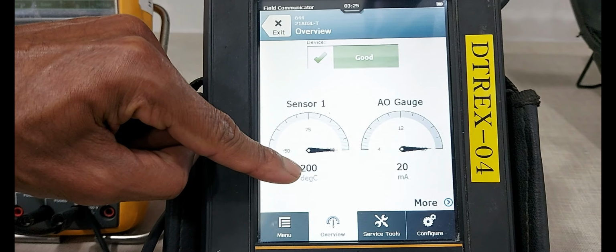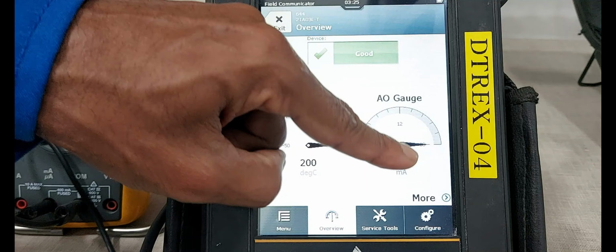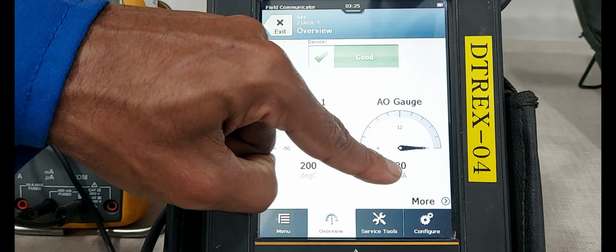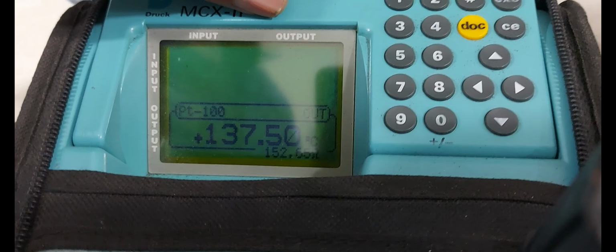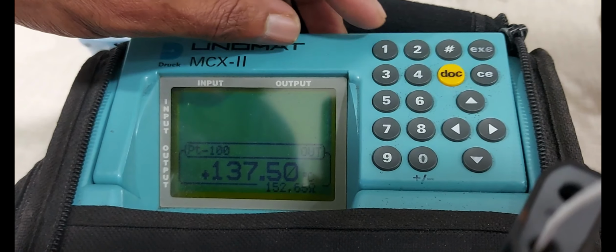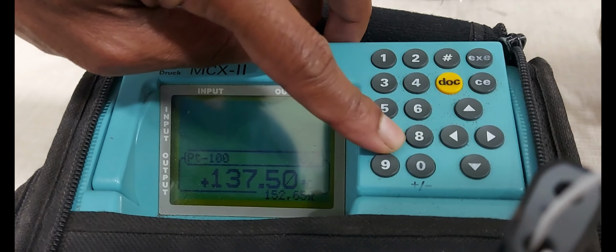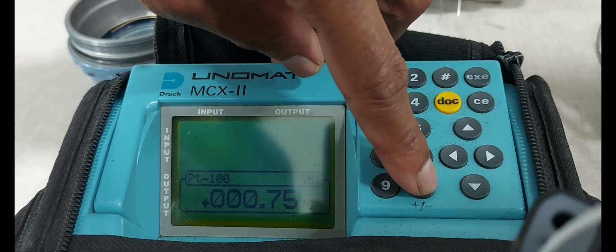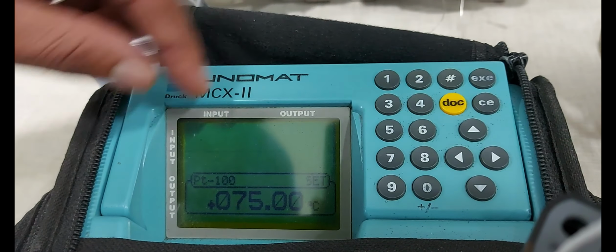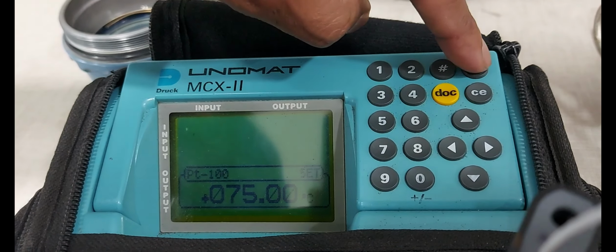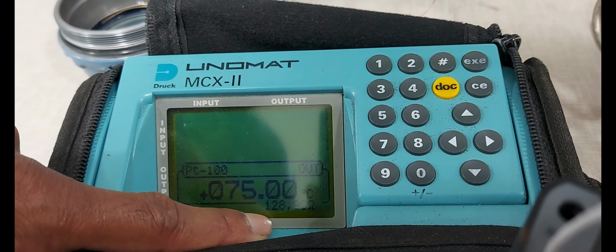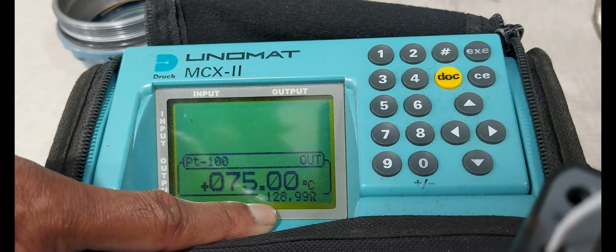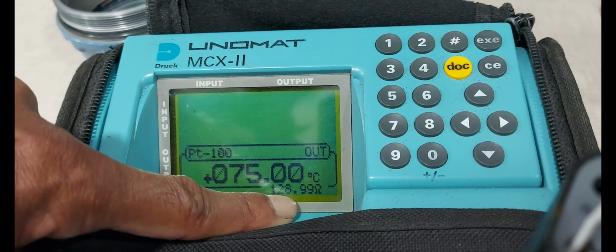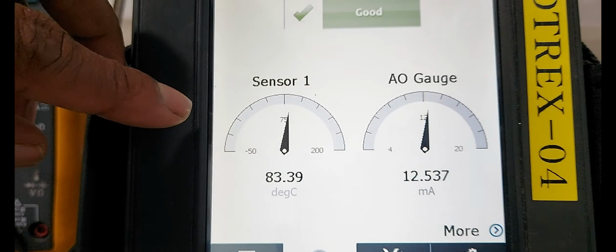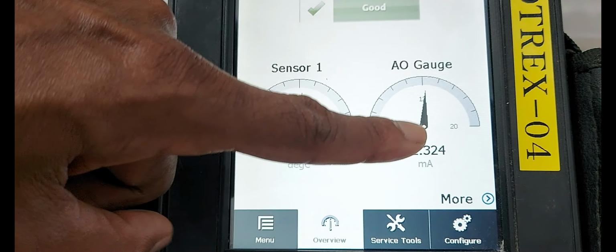Applied reference value 200 degree, output is showing 20 milliamps. Next we are applying 50% of value. 75 degree is 50%. Enter it. The resistance value is showing 128.99 ohms. Now the transmitter is settling down.